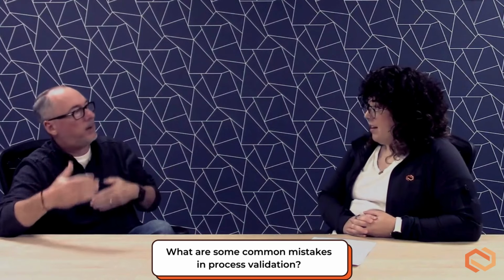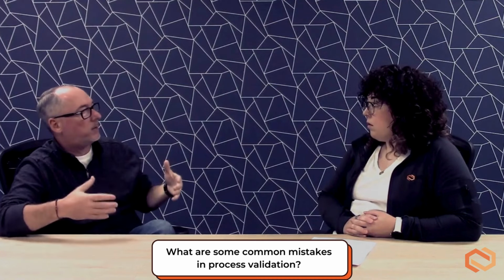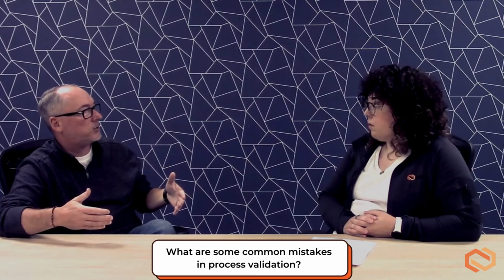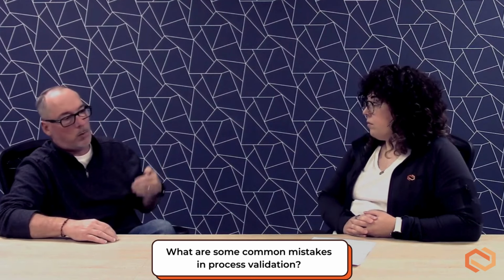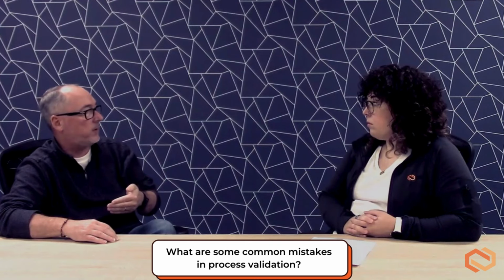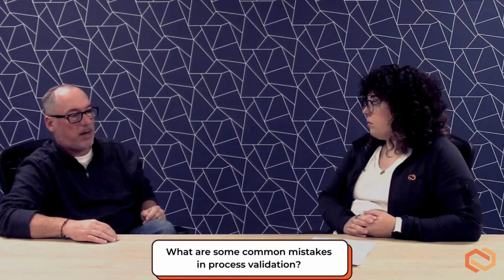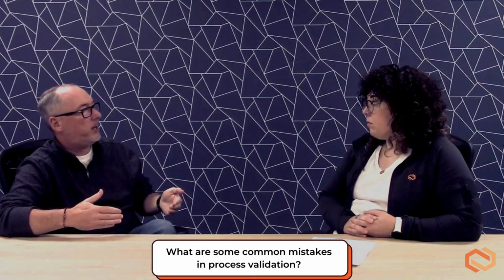Every day I run into the same issue. The strength values are all over the place, right? And then stepping back, trying to understand what they did further in the process validation is key. Or we end up with tray packages or pouches that are oversealed. It's an extremely common mistake. So stepping through that process validation is key and critical.